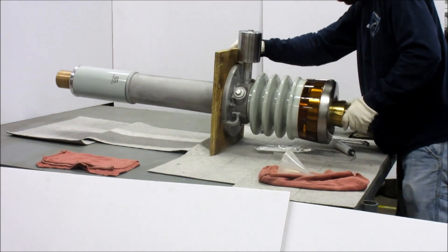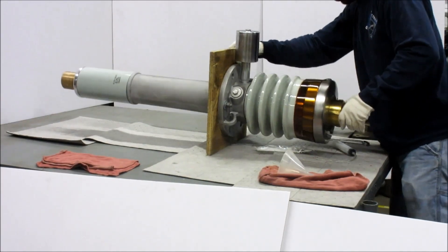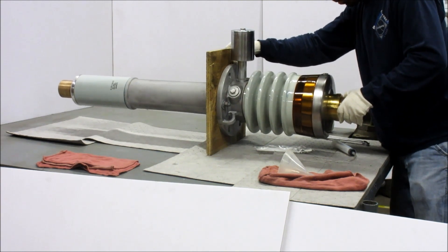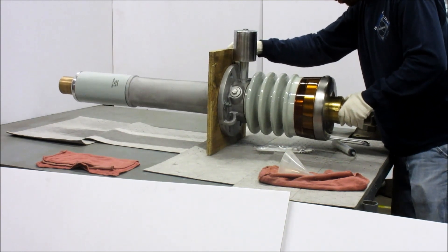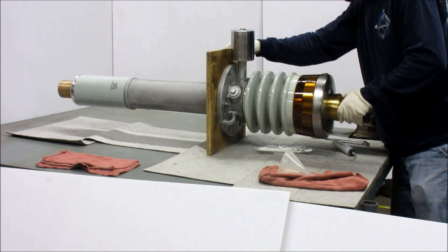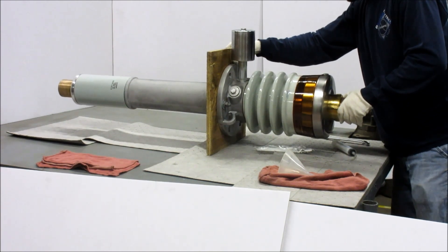Rock the bushing back and forth while keeping the oil expansion reservoir above the bushing to release any entrapped air remaining in the bushing. Watch the sight glass for air bubbles. Continue rocking until no air is being released into the glass. If the air bubble in the sight glass is larger than one quarter inch, repeat step six. More oil may have to be added to the reservoir.